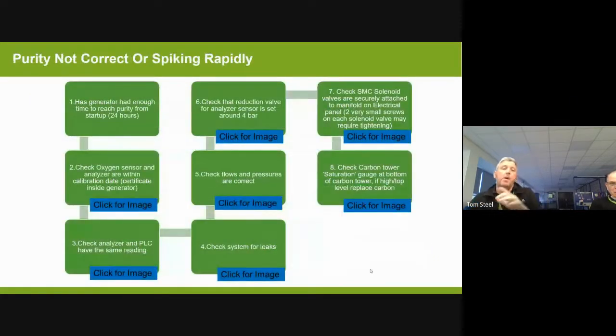We're going to have a quick look at purity that's not correct or spiking rapidly. So we need to ensure the generator has had enough time to reach purity from startup. Now you need to consider everything that's involved in this. When you first receive the generator, it will be empty. We don't store oxygen and send it with it. All the tanks and pipework will just be at ambient pressure with ambient air. So we need to ensure we can flow this through the system for up to 24 hours to clear the system of anything we don't want, so we can reach the purity of gas that's required.